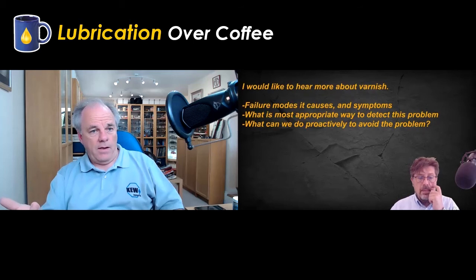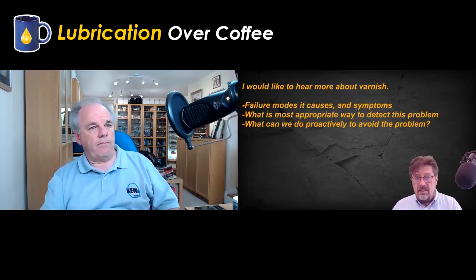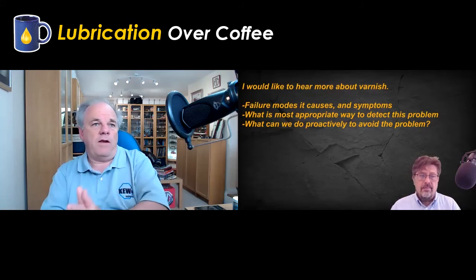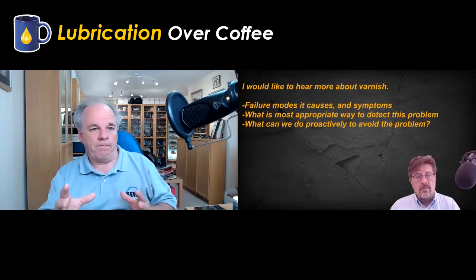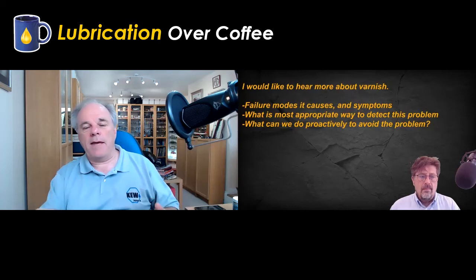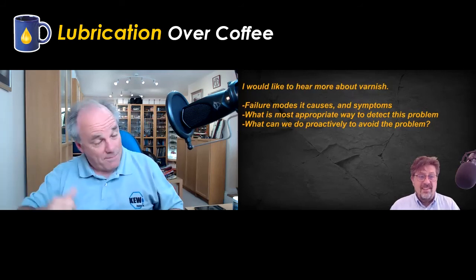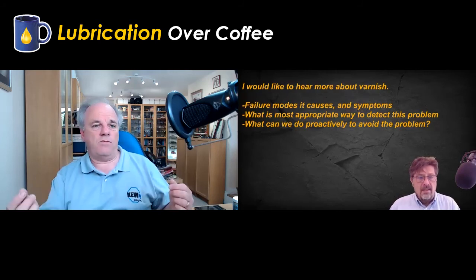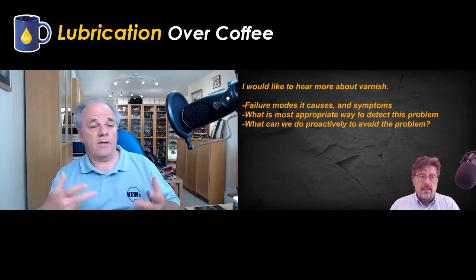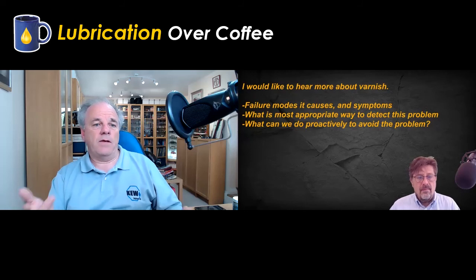Certain brands have also been more associated with the problem, which comes down to additive formulation — specifically phenyl alpha naphthylamine (PANA), one of the affected additive types. However, this is now largely a level playing field among brands, as the industry has understood and addressed that problem, so brand differences are much less of an issue today.